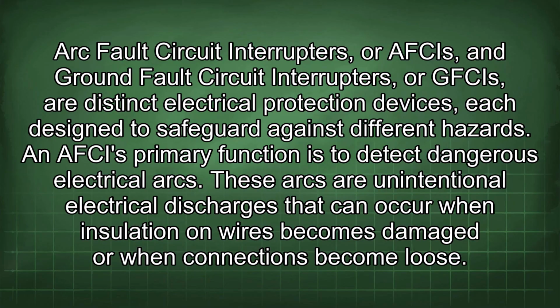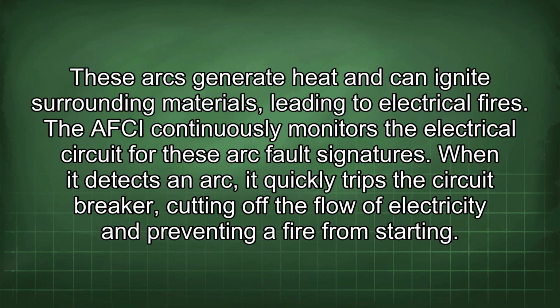Arc fault circuit interrupters, or AFCIs, and ground fault circuit interrupters, or GFCIs, are distinct electrical protection devices, each designed to safeguard against different hazards. An AFCI's primary function is to detect dangerous electrical arcs. These arcs are unintentional electrical discharges that can occur when insulation on wires becomes damaged or when connections become loose. These arcs generate heat and can ignite surrounding materials, leading to electrical fires. The AFCI continuously monitors the electrical circuit for these arc fault signatures.